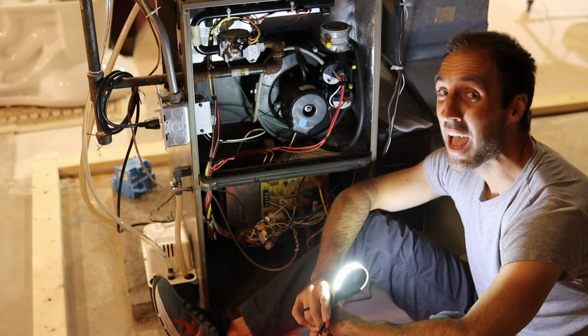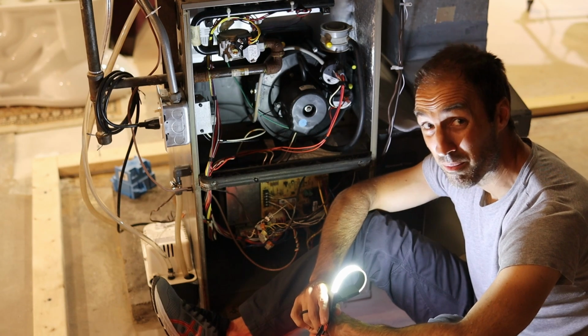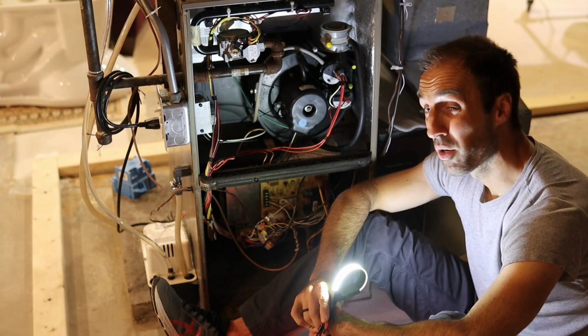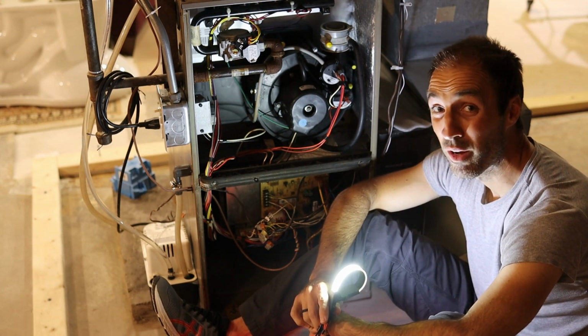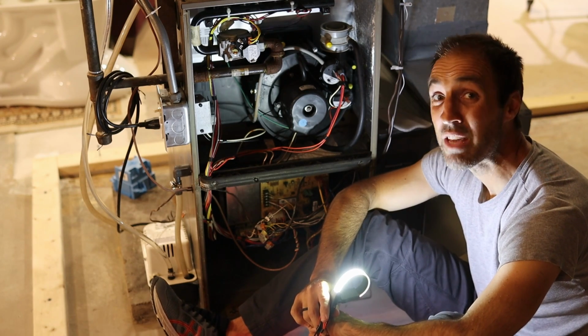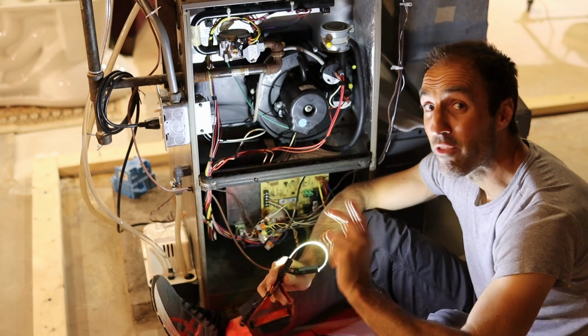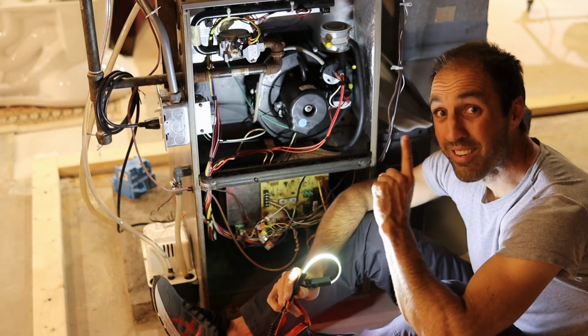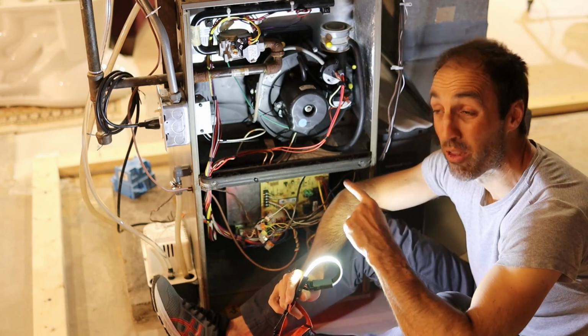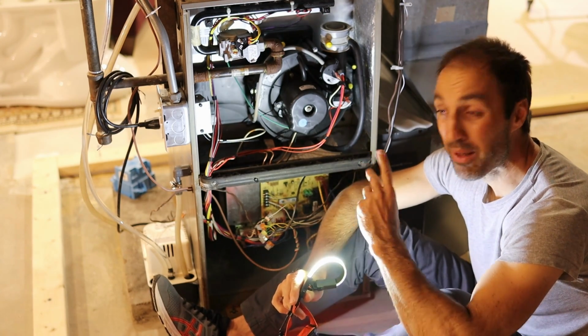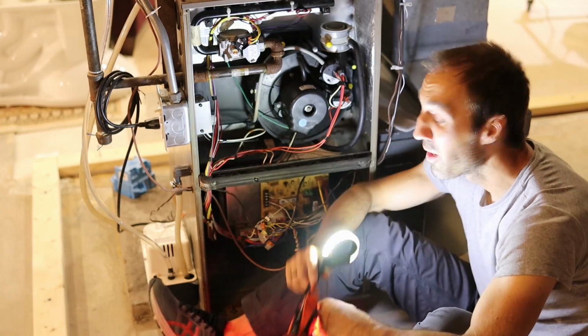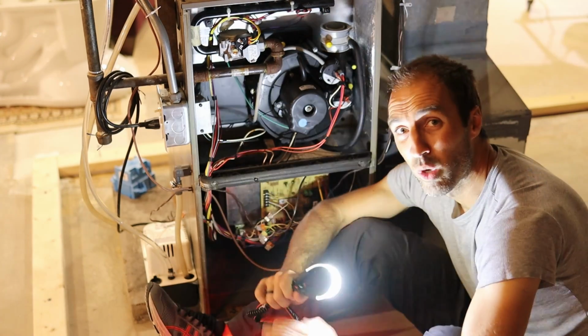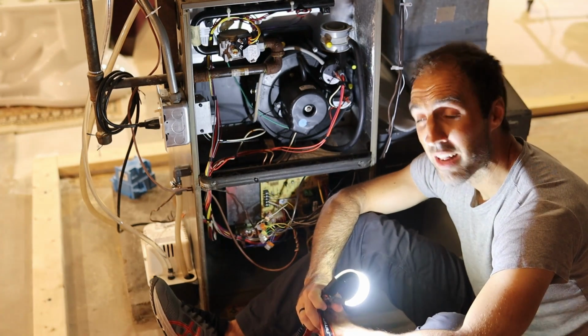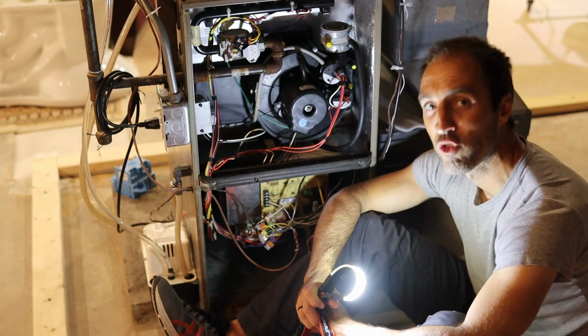So if you already have high static pressure in your system, you don't want to put in a high MERV rated filter because that's going to increase your static pressure even more. And that's going to mean two things. Number one, less air is going to be delivered to each of your rooms. So that means less heating in the wintertime and less cooling in the summertime. And two, that's going to make your blower motor work really hard all the time, and it's going to burn out your blower motor sooner.